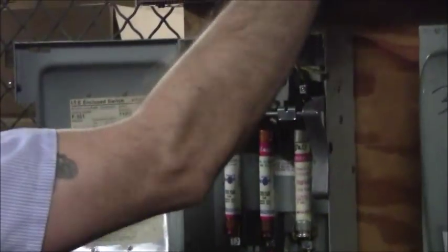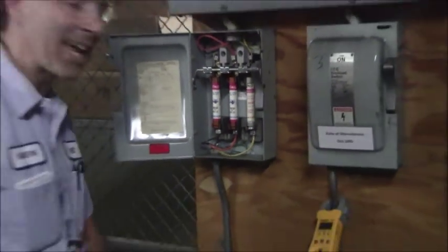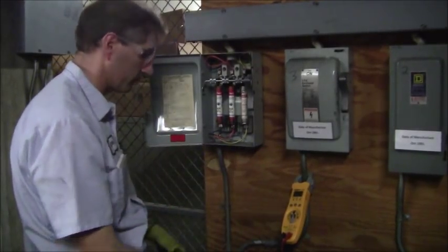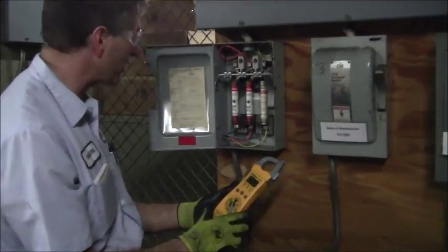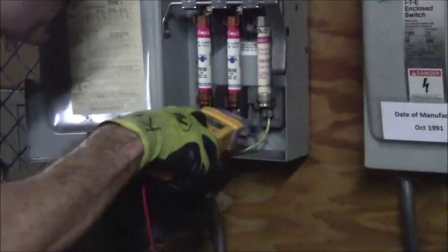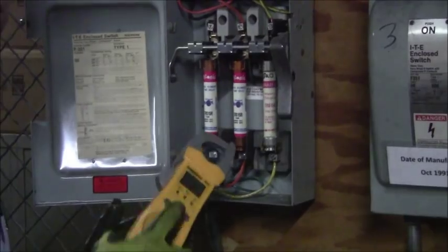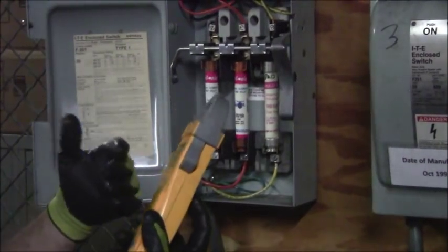Usually the electricity comes in, comes down, goes through the fuses, comes out, and then it goes to your condenser or whatever it is that you're servicing. So the first thing I'm going to do is go to voltage AC. Actually, on my meter, I can leave it in the off position and I have an NCV, non-contact voltage. I can push that in and see if anything is live. So it's non-invasive to me, I'm not touching to make sure that everything is disconnected.